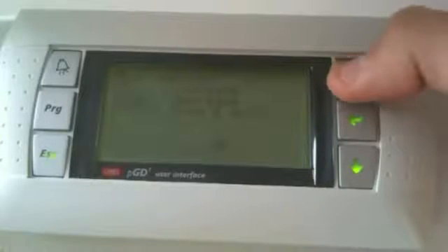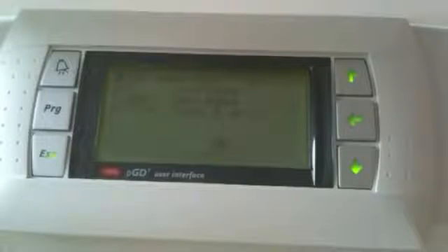You can release your hands when 'PLAN address 0' appears — this is the PLAN address of the controller. By pressing up and down (not Enter), you can set the address of the controller from 1 through 31. Within a PLAN network, each controller must have its own unique address, whereas a display can be configured as shared, thus viewing more than one controller. In this case, I only have one controller in the network and I will assign address number one.